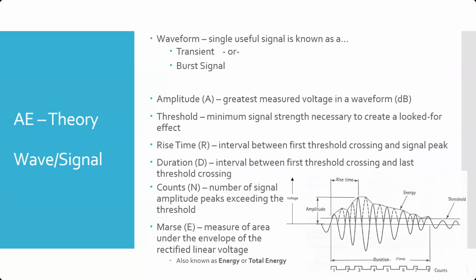When we're performing acoustic testing, what we're looking for is an event or some kind of a useful signal. A single useful signal is known as a transient or burst signal. This is typically a signal that is different than the normal noise that's taking place. If we know the normal noises an object is making, and all of a sudden it changes, or there's a short-duration event like a pop. You can think of it in the auditory range as a pop kind of sound. Right? That's what we're most interested in when we're performing acoustic emission.